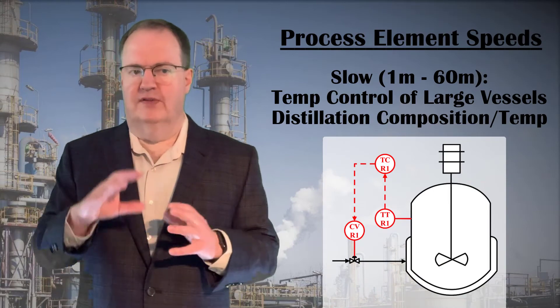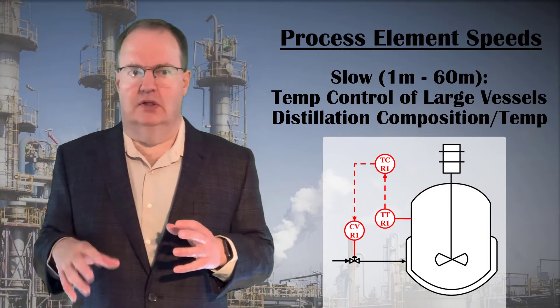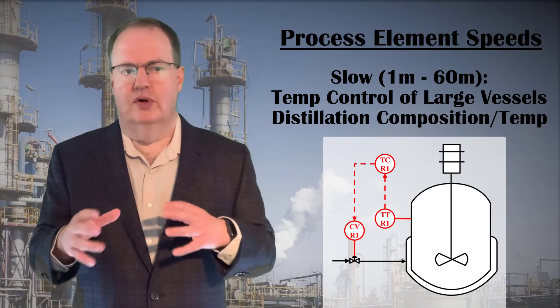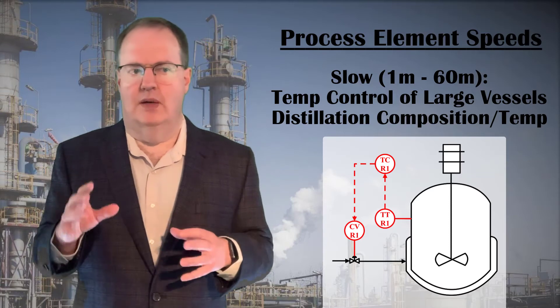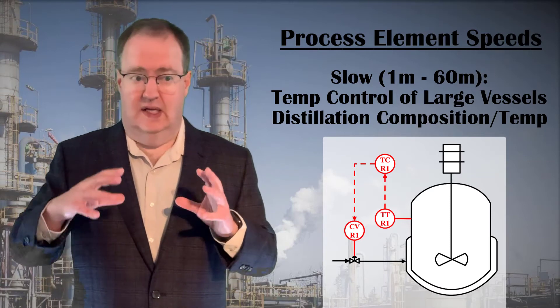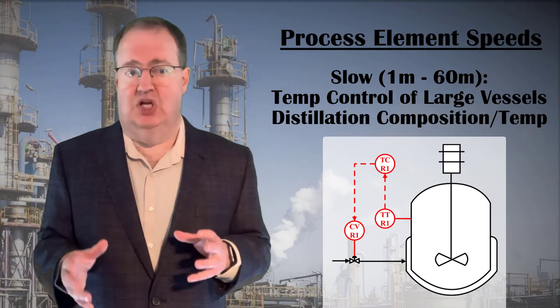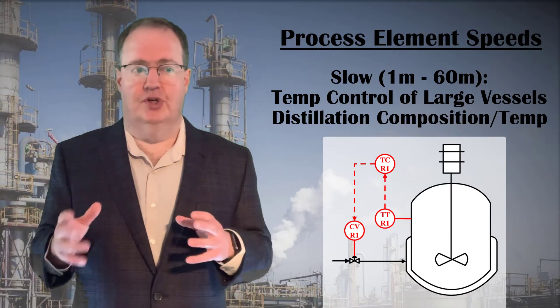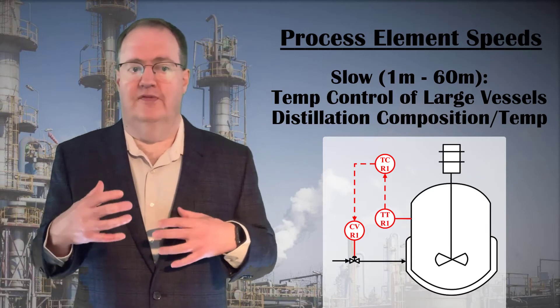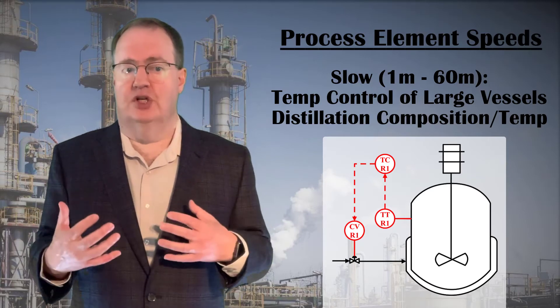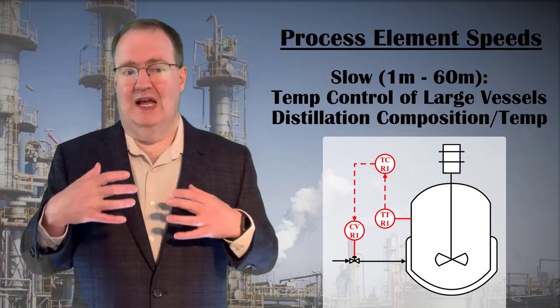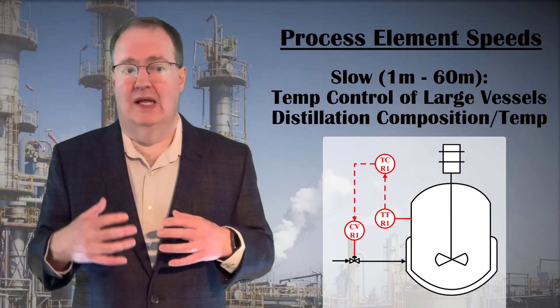Temperature control of a large vessel, like a stirred tank reactor, could have a dead time of one minute with a time constant of up to 10 minutes. Distillation column temperature control, from which we can infer composition, can have dead times of several minutes and time constants of up to an hour.